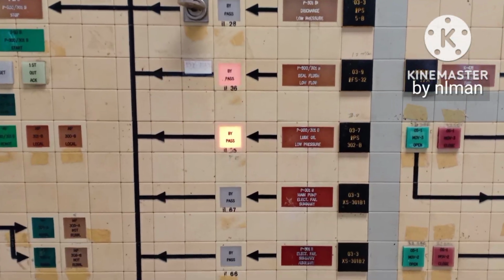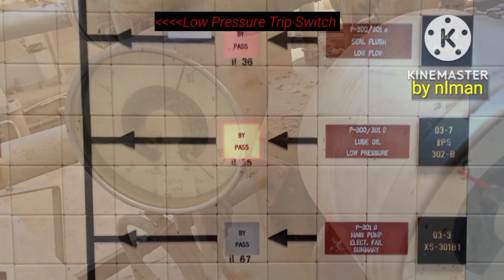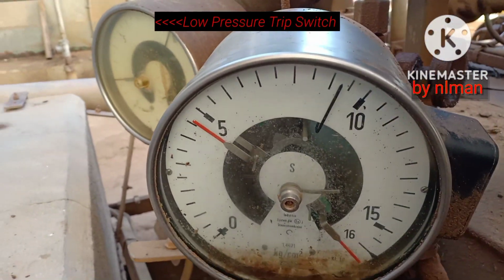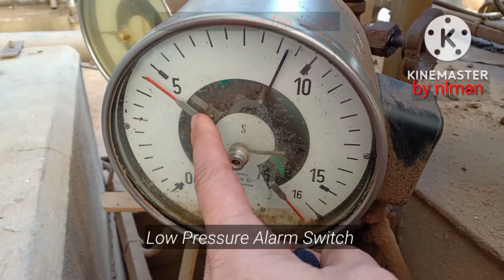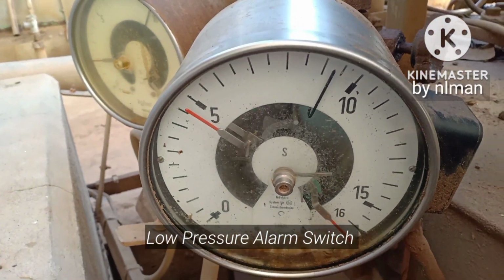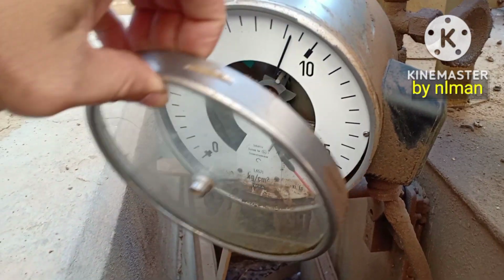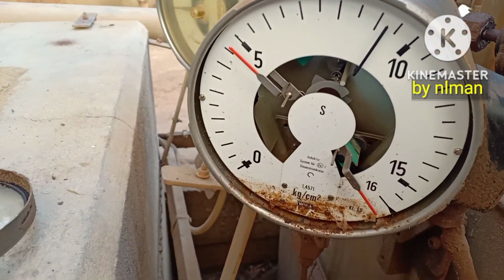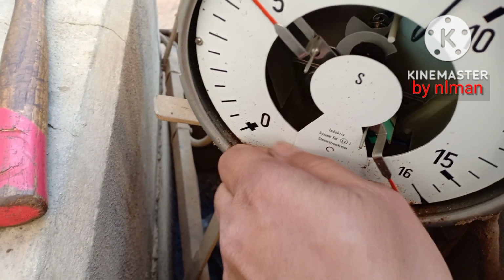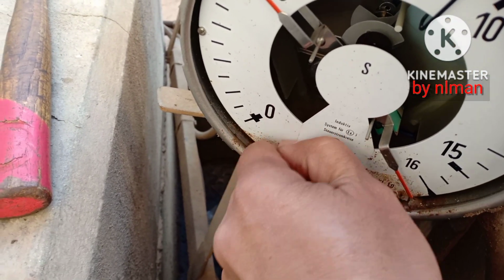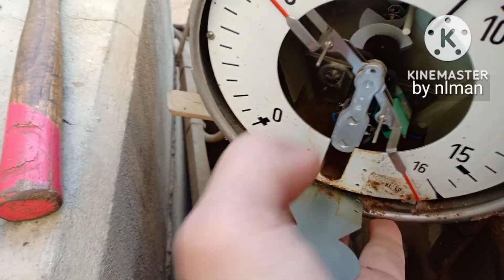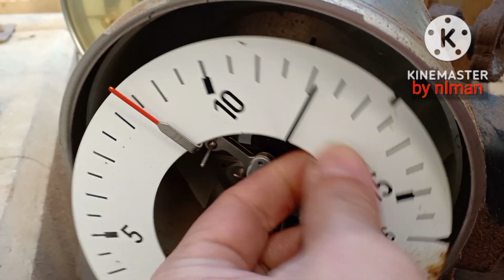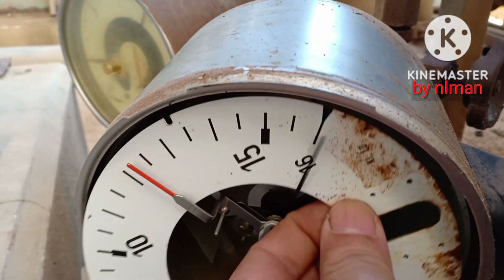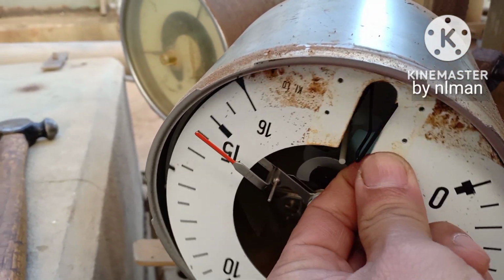Hello, good day to everyone. Since the plant is running at full capacity, before we execute checking and replacing the switch for the low pressure alarm switch, we must first override the low pressure trip switch for safety reasons, so that we will not disturb the plant, because now the plant is running normal.